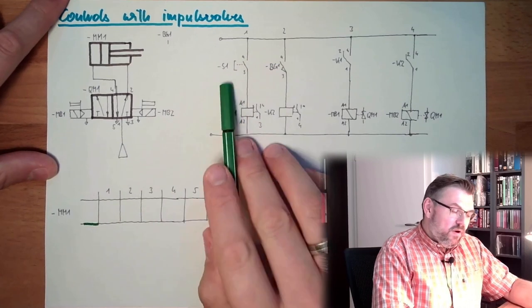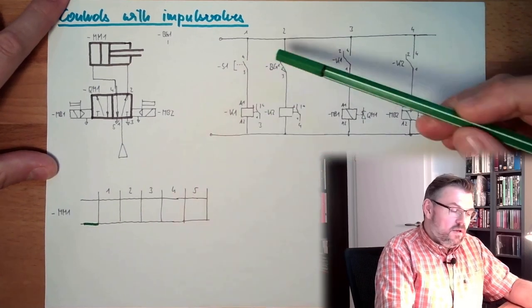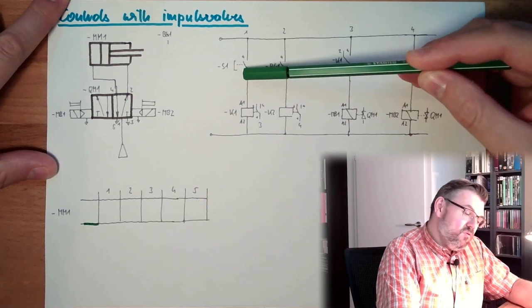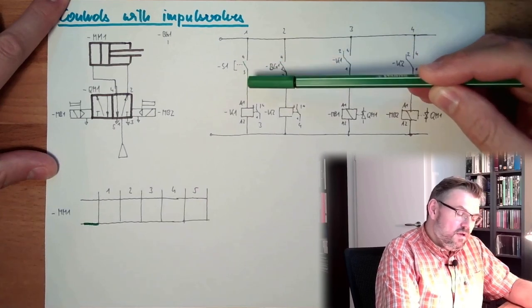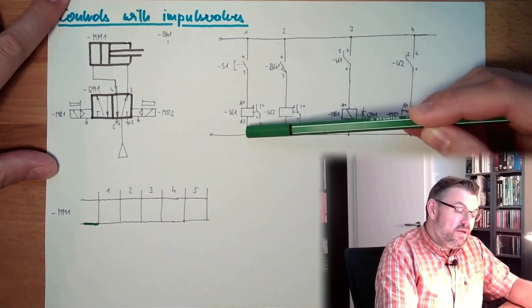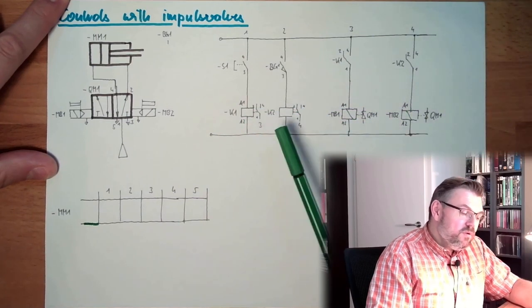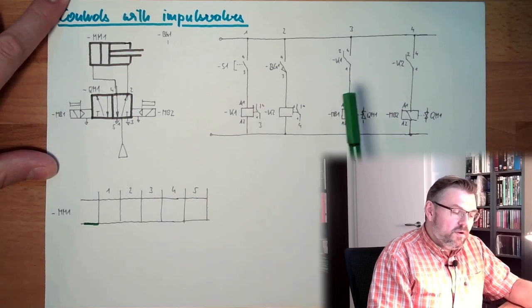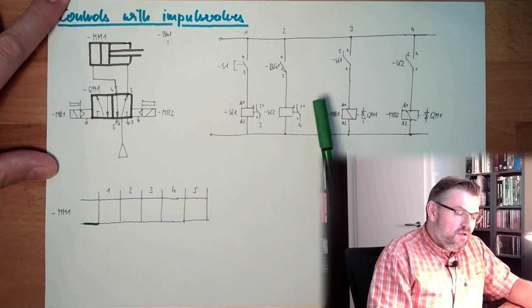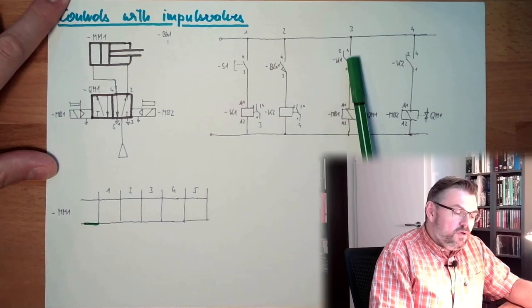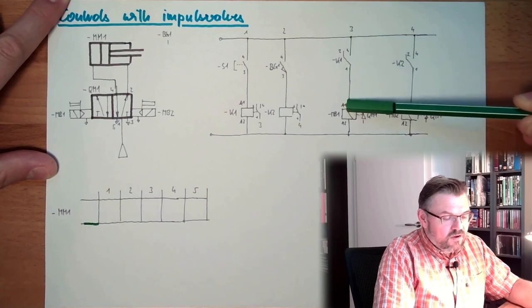Then somebody is pressing button S1, okay? Then we have here, this normally open contact is closed. K1 is energized, the coil of K1 is energized, and it will switch. It will switch from normally closed to normally open contact. If here this K1, it's in path number three. If here this K1 is now switched, we have here a connection. The connection will energize MB1.